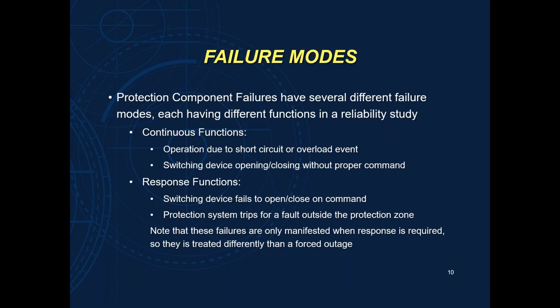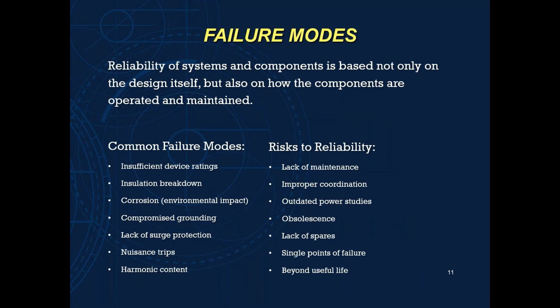So the point of this is not to know each and every one of these types of failures. It's more to understand how many different parameters are out there that you can consider when you do a reliability study. Because a reliability study can be as complicated as you would like it to be or as simple as you'd like it to be. Of course, the more complicated, the more accurate it's going to be. So here are some common failure modes that we can talk about. You have insufficient device ratings, you have nuisance trips because you're not coordinated properly. You might not have sufficient grounding, and so you might be subject to some transient voltage spikes, surges, things like that.